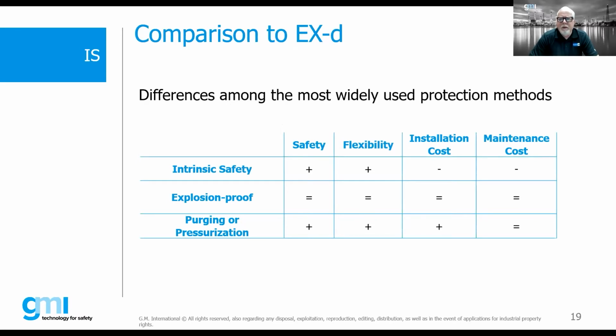People always ask, well, what's the most cost-comparative or cost-effective means of EX protection concepts? So intrinsic safety is considered to be, literally, when used correctly, one of the safest protection concepts. As a matter of fact, it's one of only two protection concepts actually approved for zone 0 applications. It certainly offers flexibility. There is some associated installation cost, since you have to take into account some segregation between IS and non-IS.